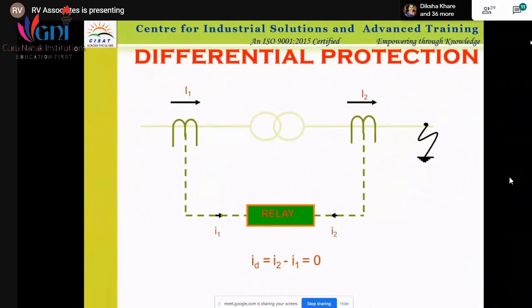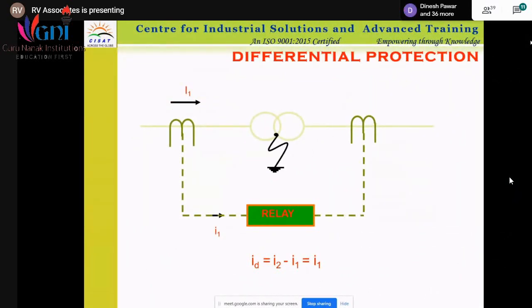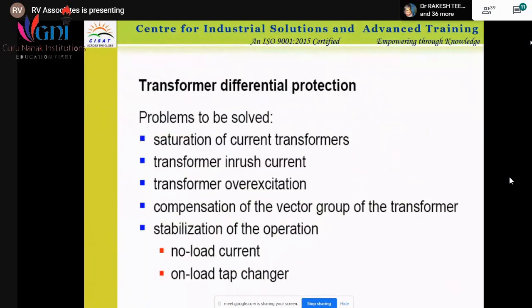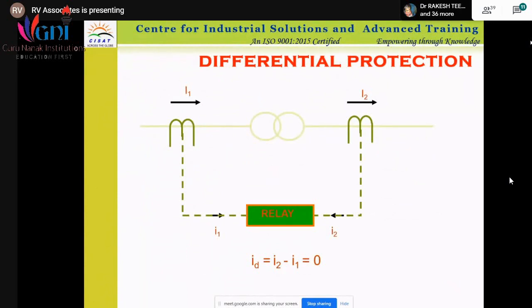We are not talking about the different protection systems here, but this is the differential protection, how it works on a transformer. Two CTs are connected, one in primary and one in secondary. The difference between the currents in the two CTs is measured, and accordingly the relay acts. There are some standard practices, like on the star side winding, delta CT to be used, and on the delta side winding, star CT to be used, and connections are there for 3-phase 3 windings.